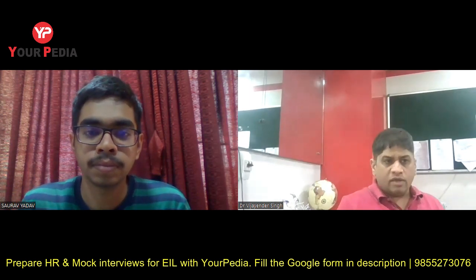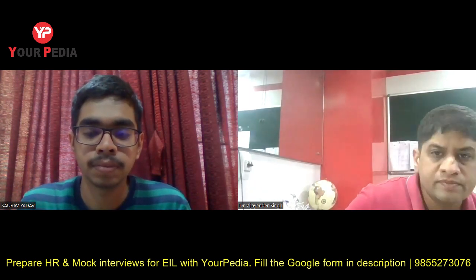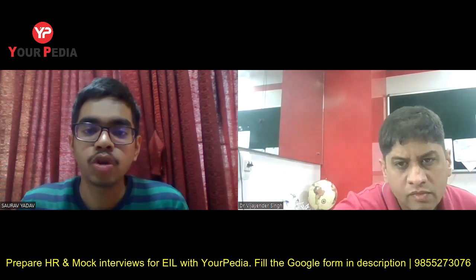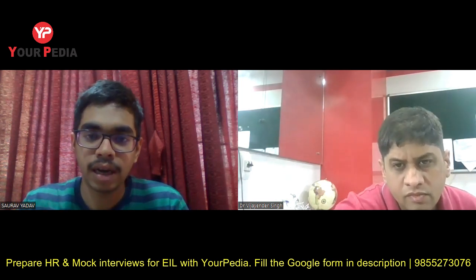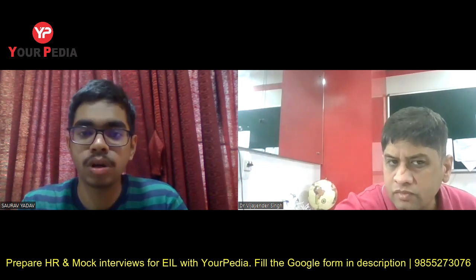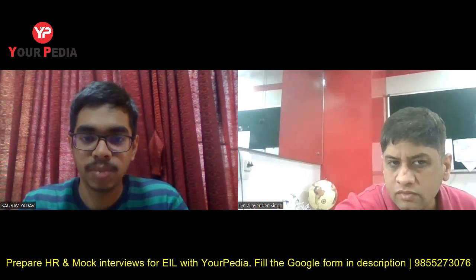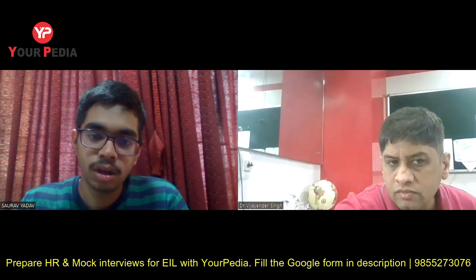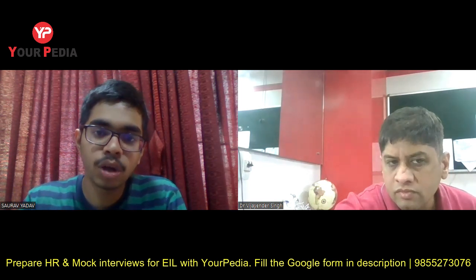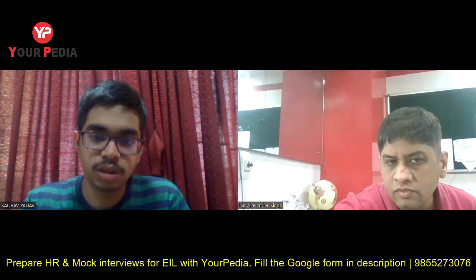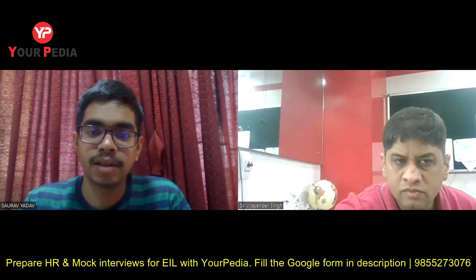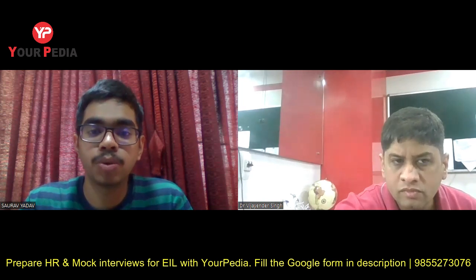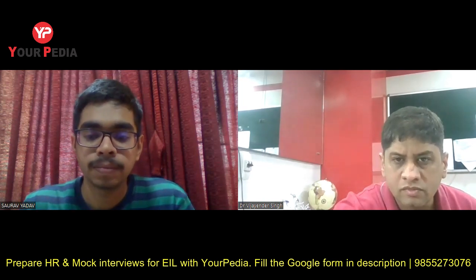Okay, can you tell me, Saurabh, what is the draft tube? Yes, sir. Draft tube is an instrument which we use so that the kinetic energy of the outgoing water is not wasted much and is converted into useful energy as much as possible, and it allows us to place the turbine above the tail race level so that we can take care of the maintenance without reducing the power output of the turbine.